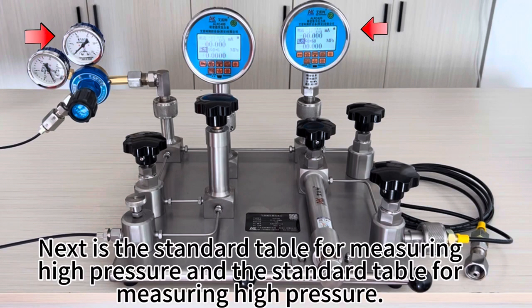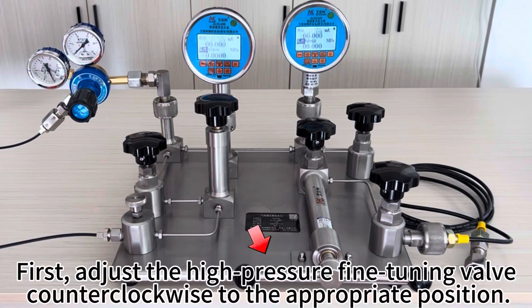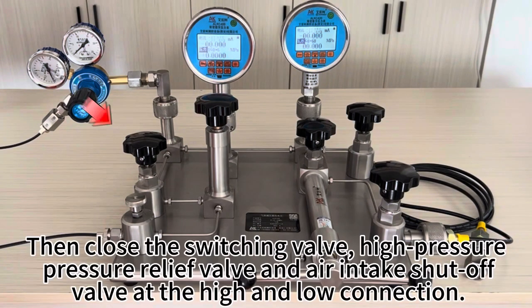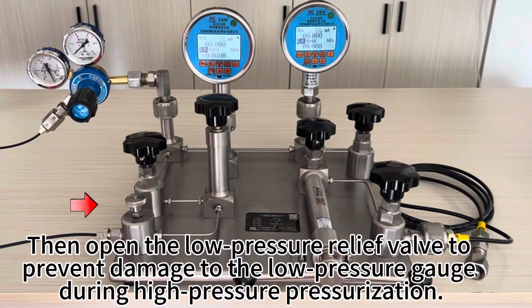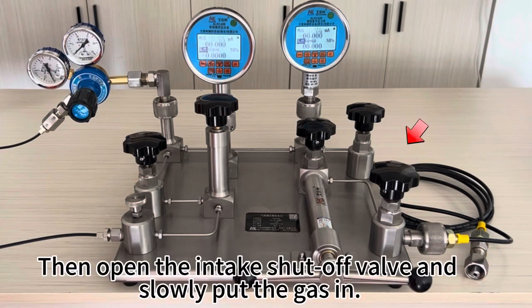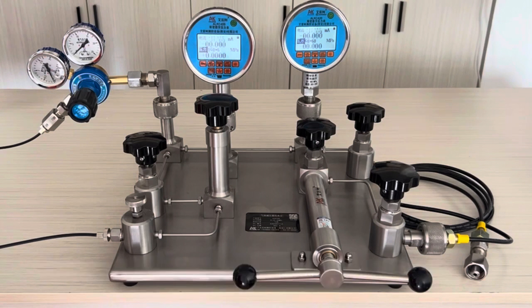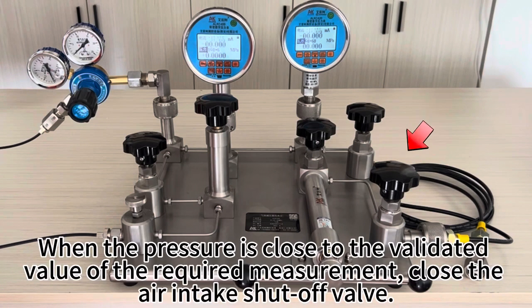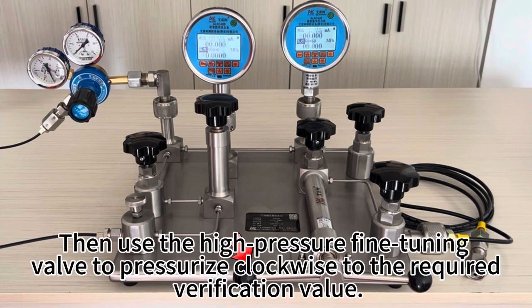Next is the standard table for measuring high pressure and the inspected table for measuring high pressure. First, adjust the high pressure fine-tuning valve counterclockwise to the appropriate position. Then close the switching valve, high pressure relief valve and air intake shut-off valve at the high and low connection. Then open the low pressure relief valve to prevent damage to the low pressure gauge during high pressure pressurization. Then open the intake shut-off valve and slowly put the gas in. When the pressure is close to the validated value of the required measurement, close the air intake shut-off valve. Then use the high pressure fine-tuning valve to pressurize clockwise to the required verification value.